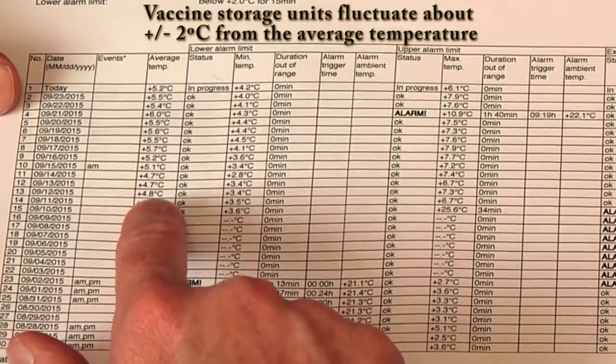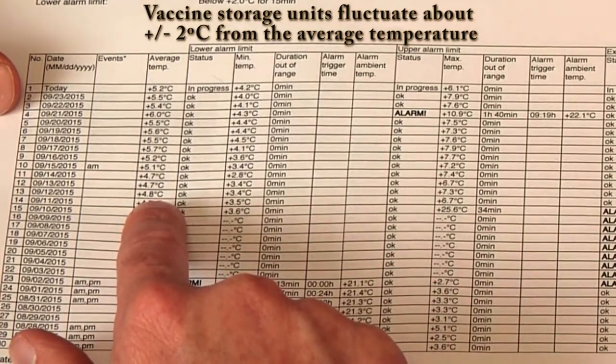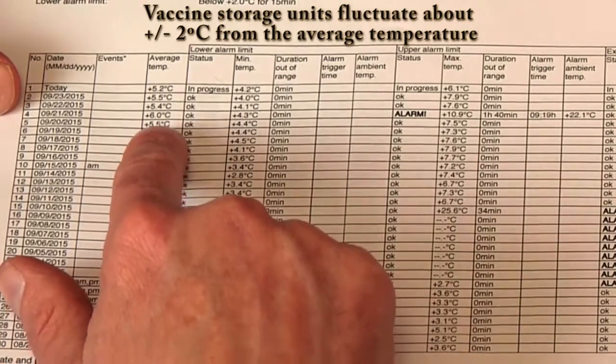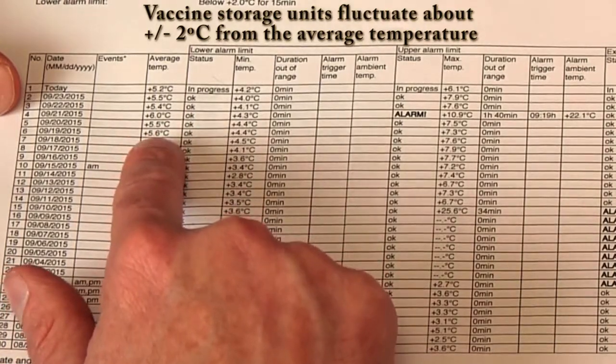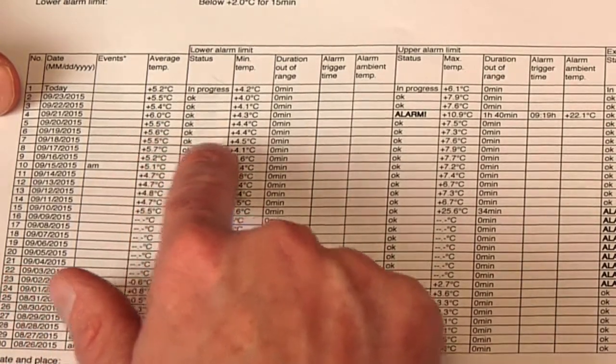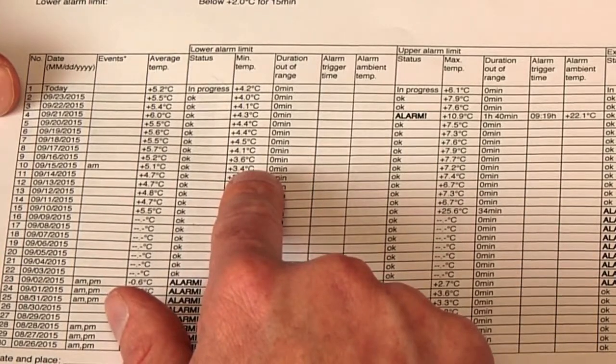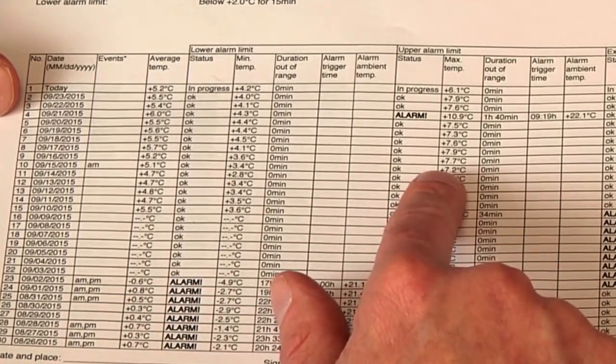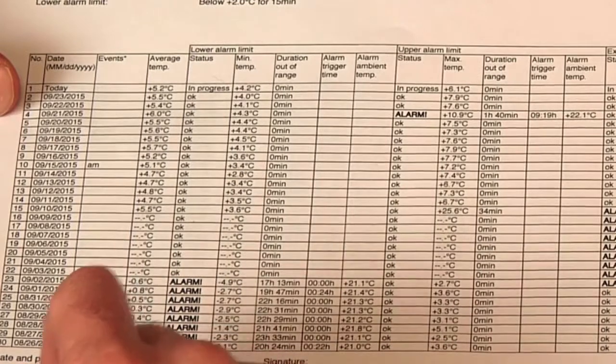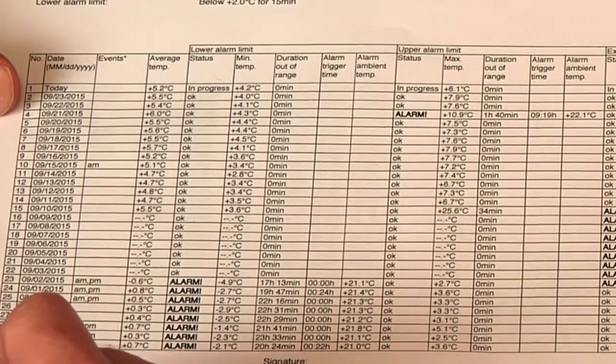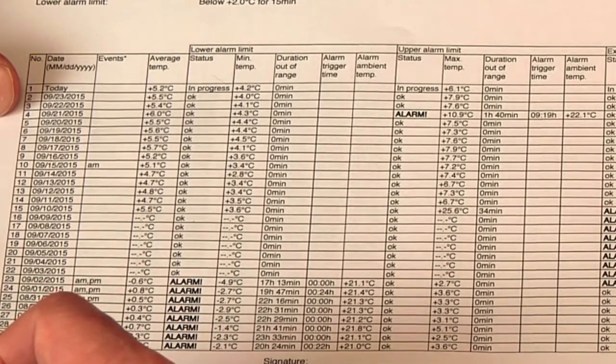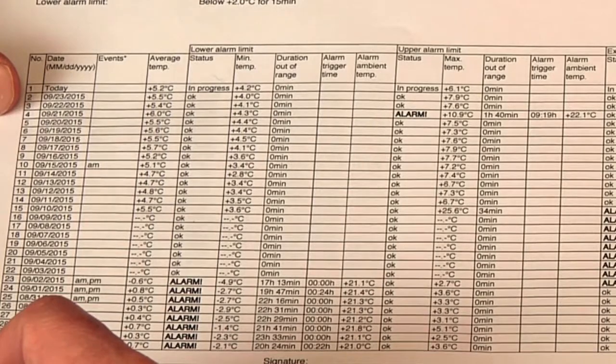And by adjusting the temperature up slightly in this storage unit, taking the average closer to 5 degrees C, we can see that the low temperatures move within range and the high temperatures move within range. And this storage unit is now an acceptable environment for storing vaccines and biologicals.